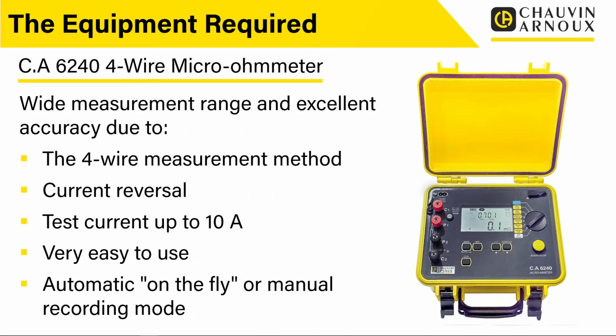So now moving into our entry level, shall we say, 4-wire micro-ohm meters. This is the CA6240. This is by far one of the most popular 4-wire micro-ohm meters. We sell a lot of these. There's a lot of these in circulation all over the place, and I think they're probably the most popular of our micro-ohm meters, and they do most things that everybody would want. So if you are looking to get started, this really is the product that you want to be looking at. It's 4-wire measurement, so it's proper 4-wire measurement, as you can see on there.